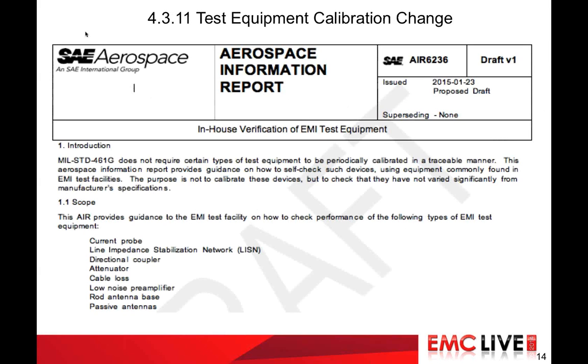So SAE Aerospace Information Report AIR 6236 contains guidelines on how to check transducer factors. It is not yet referenced in the draft for industry review because it has been voted on but not yet formally adopted by the SAE. It should be referenced in the actual release of 461G. The title is In-House Verification of EMI Test Equipment. It is not a calibration reference. The purpose is to provide a quick way to check a transducer's performance. If the performance matches recorded transducer factors, all is well. If they're significantly off, then recalibration and/or repair may be indicated.